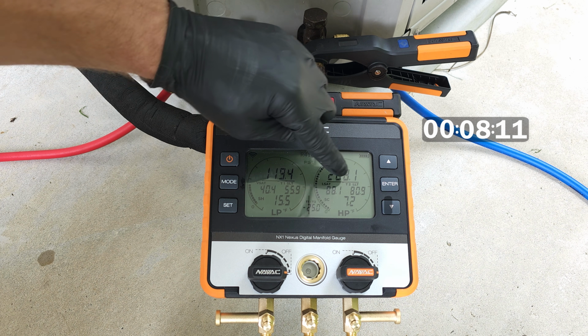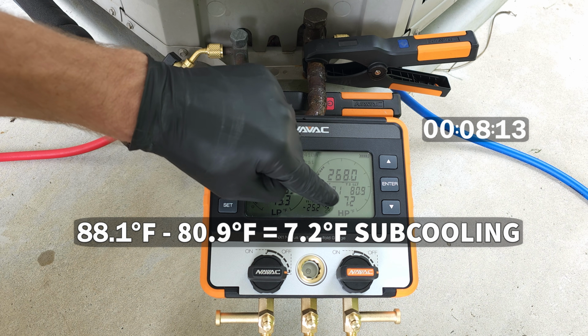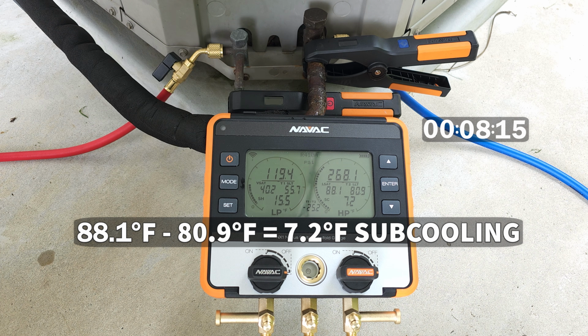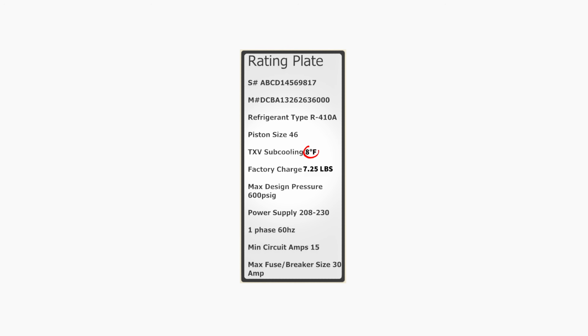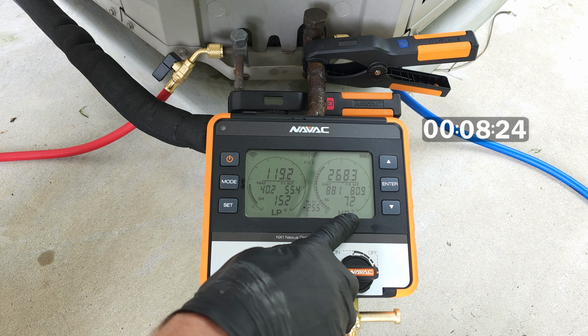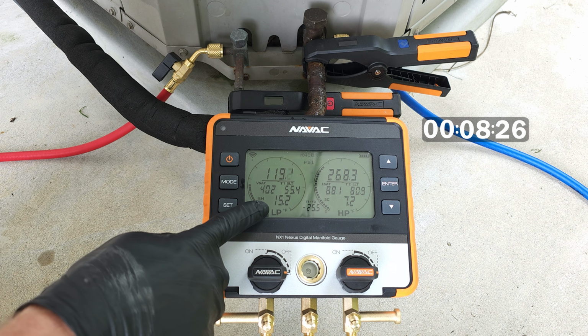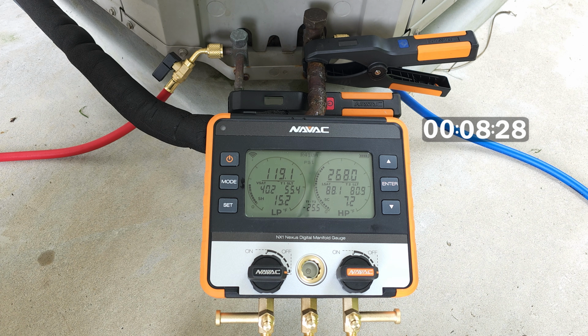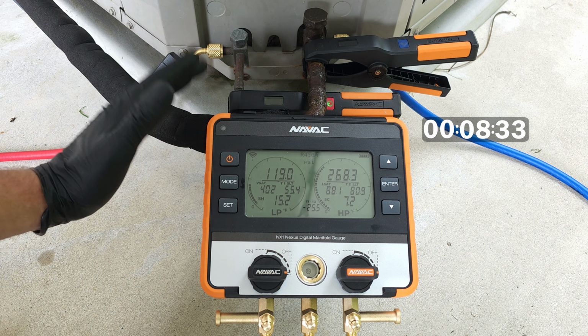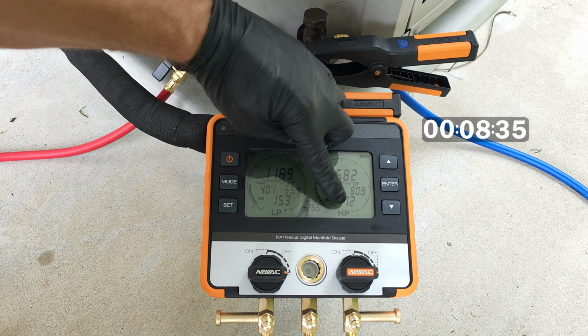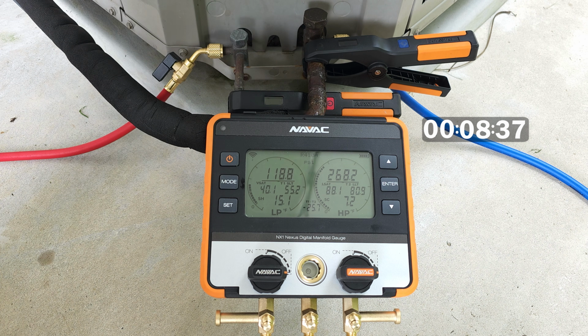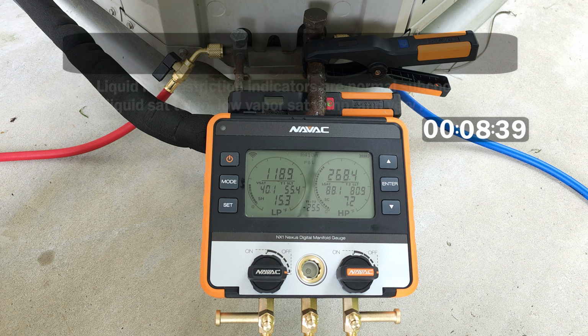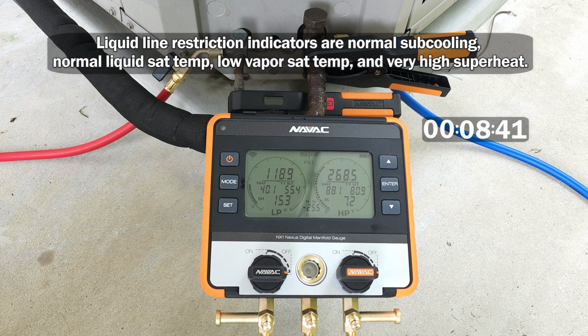So we take 88.1 minus 80.9, and we're left with a subcooling of 7.2 degrees. Up on the rating plate, it says the target subcooling is 8 degrees. So we're very close to the target. We're just a little low, but the refrigerant in this system was not the problem. As you can see here, it was that we had low airflow. So you can tell there really is no issue with this system right here. We could add a little bit of refrigerant, that's about it. But there is no other problems. It's not a liquid line restriction or anything like that.